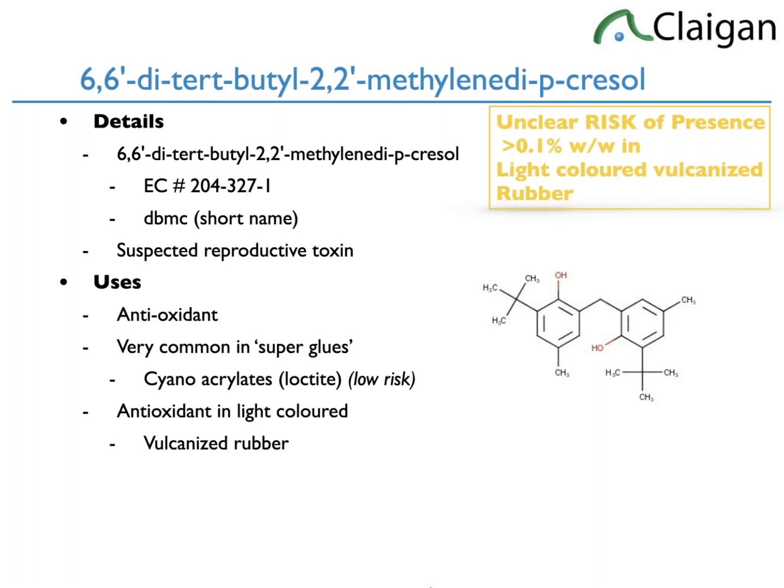However, it's an adhesive. And for REACH SVHC purposes, any residual antioxidant, which would be a couple thousand ppm in the Loctite, is measured over the weight of the cyanoacrylate and the part it's adhered onto. And if you add the weight of the part it's adhered onto, any residual DBMC is trivial mass. So it's low risk for REACH SVHC. Now we're going to see the same chemical come up later. It's not low risk for EU MDR because the definitions are different.